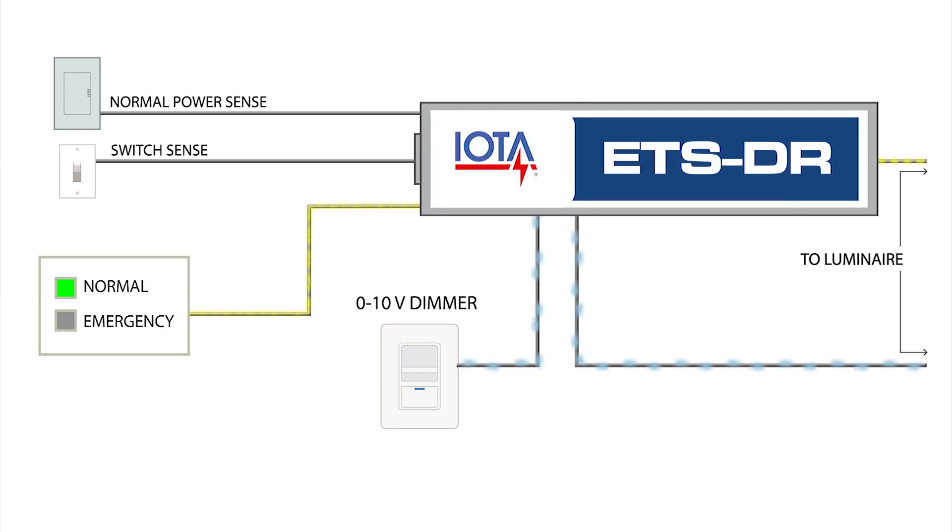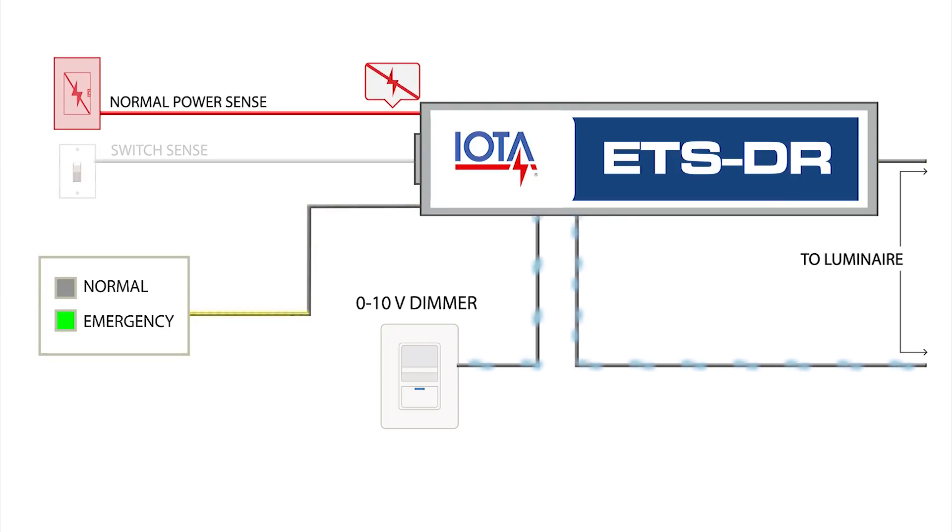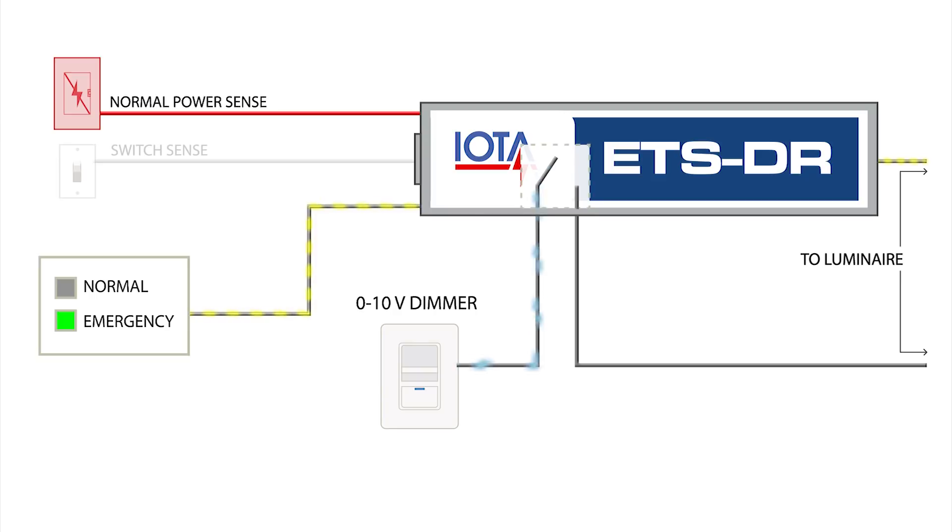However, if a normal power loss is detected, it will electrically open its dimming relay contacts forcing the luminaire to operate at full light output.